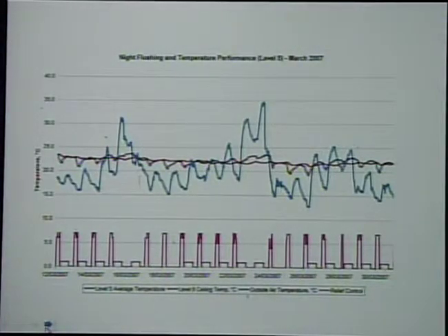The next slide shows the result. That's a good picture: the blue line is the shift in Melbourne's three-day temperature cycle, the red line is the slab temperature, and the dark blue is the resultant indoor temperature, which we've adjusted to remove the benefit of other systems, so we can identify what effect the slab and the opening and shutting of windows has overall. It gave us about a 20% cooling load advantage. The red peaks at the bottom show when we open the windows and when we don't, when the temperature gets too hot. It's simply controlled by thermostat, so that when the air temperature...